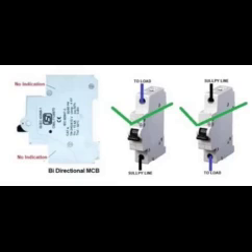You will find MCBs in the market which do not indicate any connection diagram or line and load marking. This type of MCB is called a bidirectional MCB, where you can connect your line and load at any point of the MCB. At short circuit or overload condition, this MCB will operate.